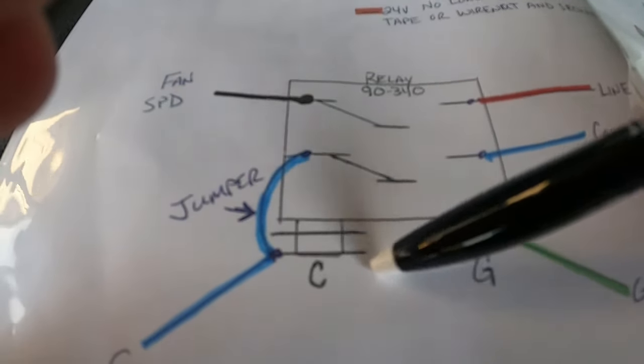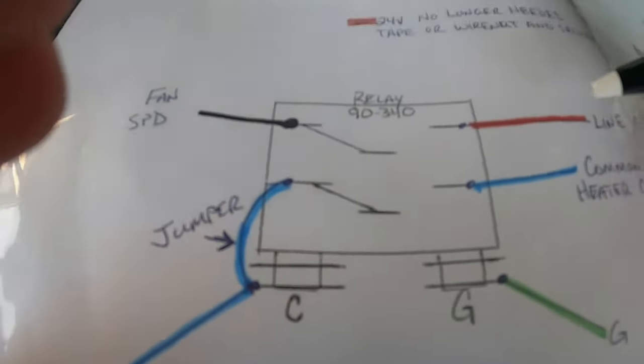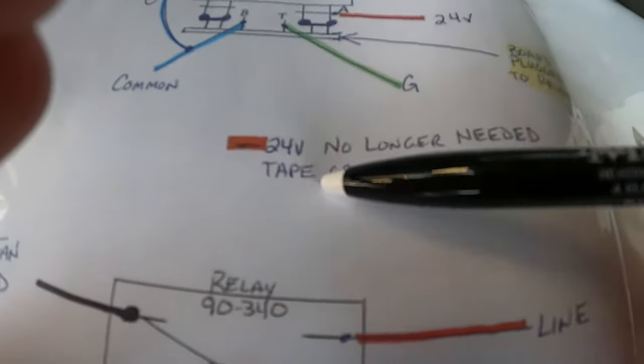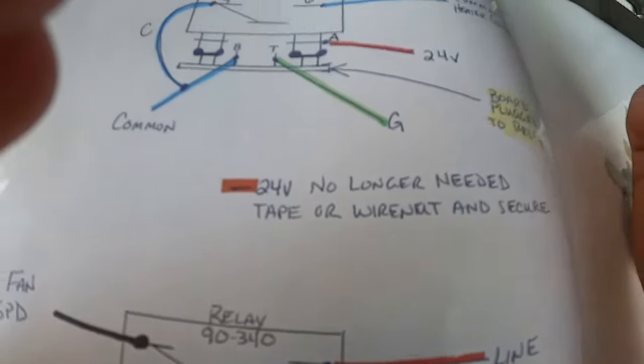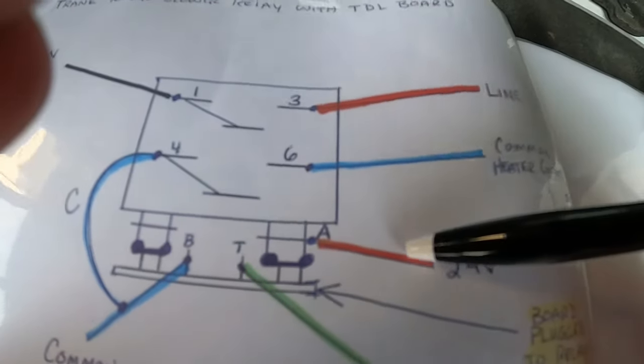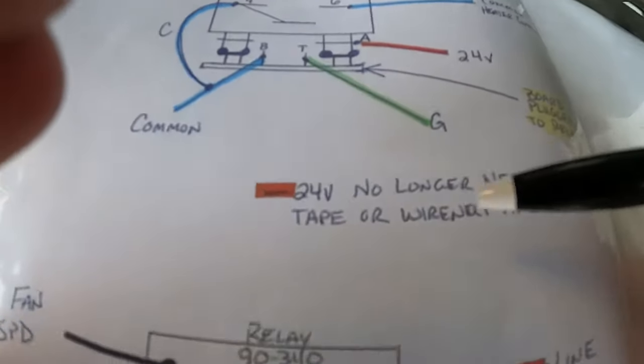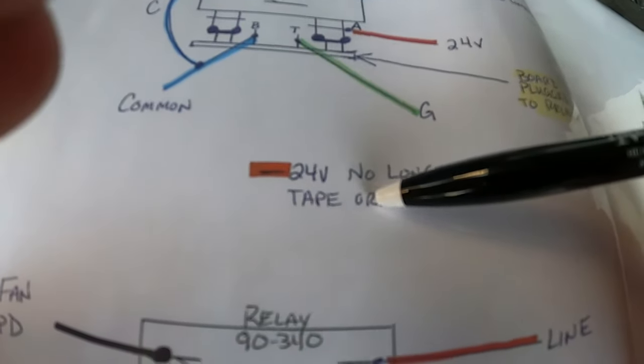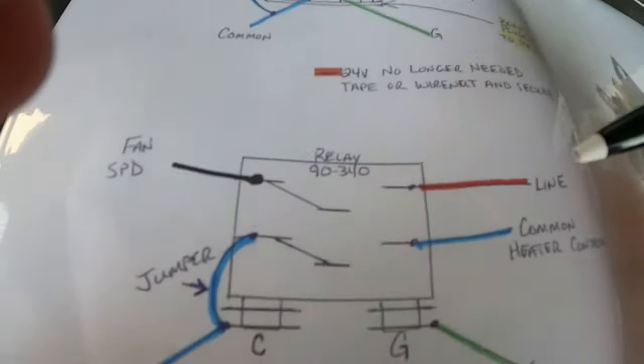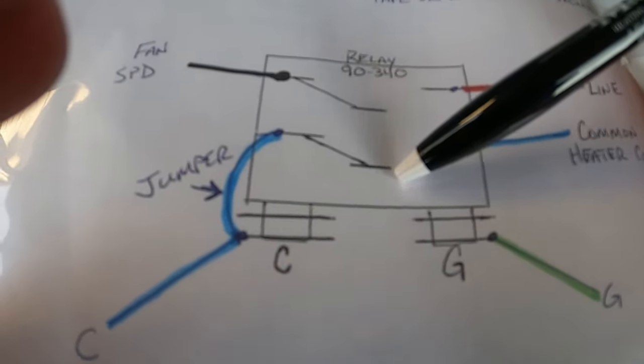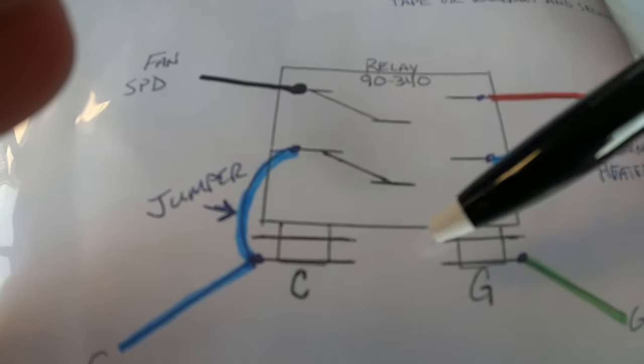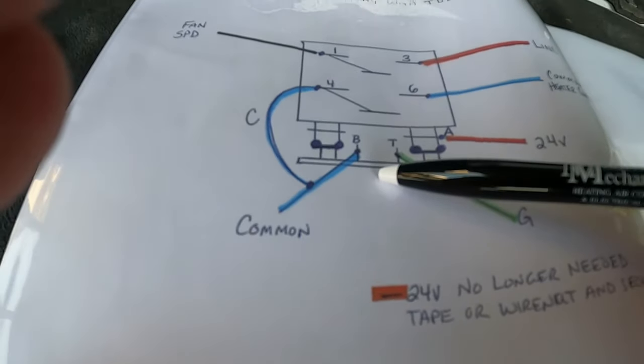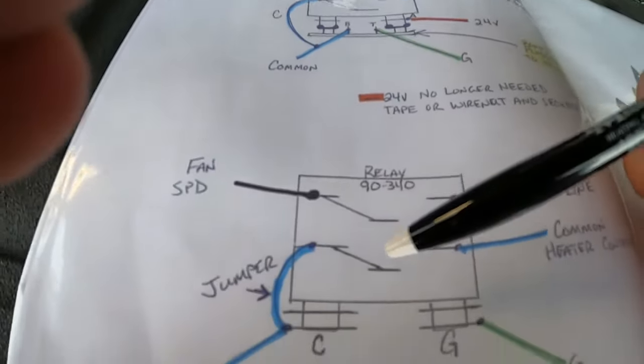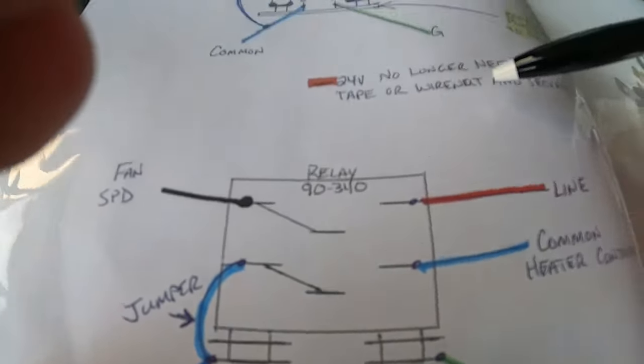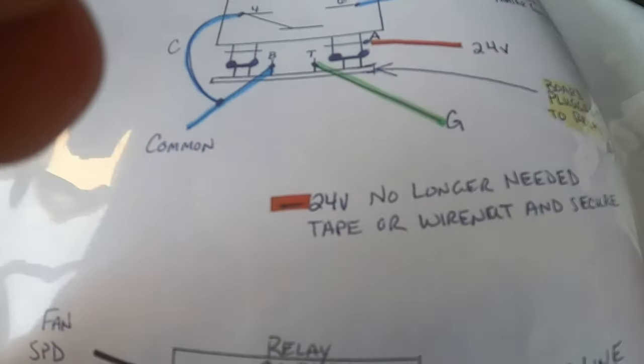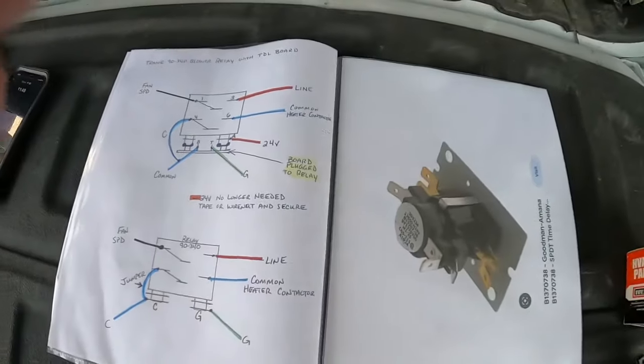So it actually kind of wires the same way. You're just getting rid of that time delay board, which means in this situation, once again, the 24 volt wire, which is here, is no longer needed. You're just going to wire nut that and put it to the side. You don't need it anymore. So this is kind of the easier version, because you're just taking the board off the bottom of it. You're going to wire it back up the exact same way. You're just going to get rid of that 24 volts that you don't need anymore.